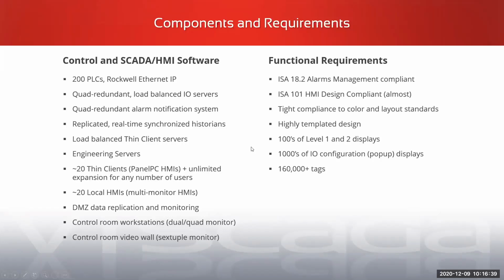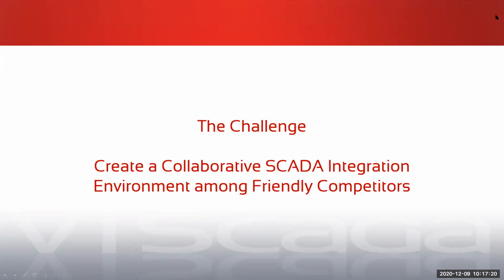Let's move into the functional requirements. The intent is for this system to be ISA 18.2 compliant for alarms and 101 compliant for HMI design. It's worth noting 'almost,' as you'll see when I show some screens — we wanted tight compliance to color and layout standards. We'll be deploying about 160,000 tags, thousands of sensors, and many screens and displays, so having a highly templated design lets us quickly roll out additional pieces.